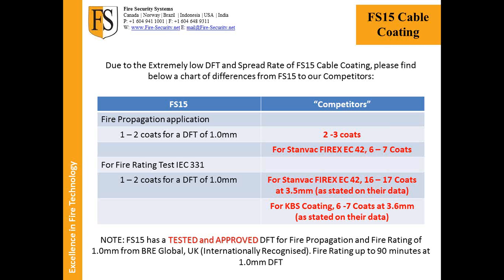So, as I've noted at the bottom of the page, you'll see that FS15 is tested and approved DFT for fire propagation and fire rating of 1 millimeter from BRE Global in the UK. Fire ratings up to 90 minutes at 1 millimeter DFT as well. We can always go back.